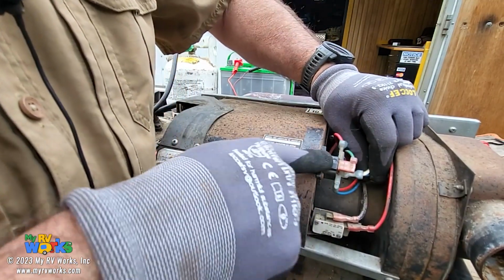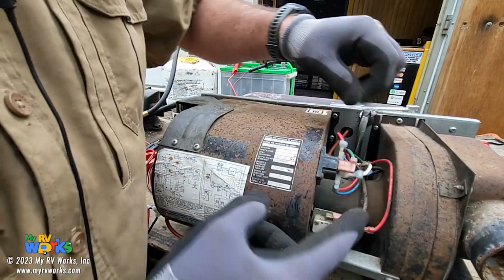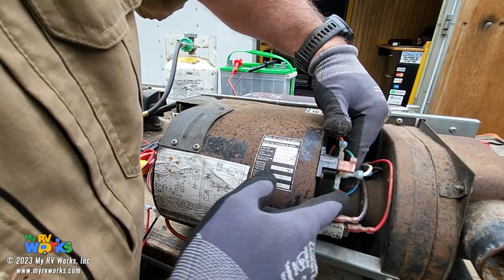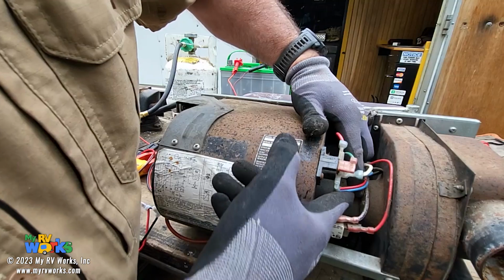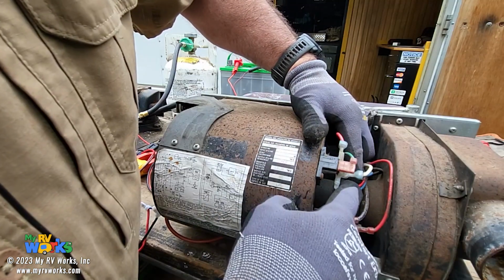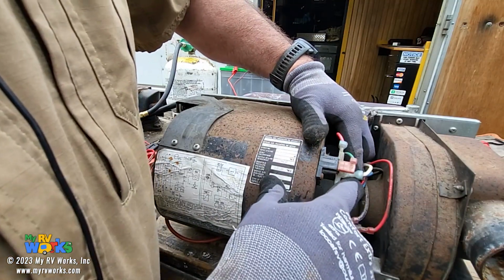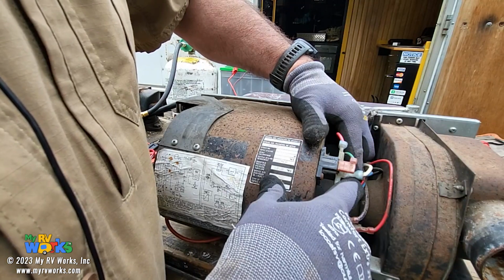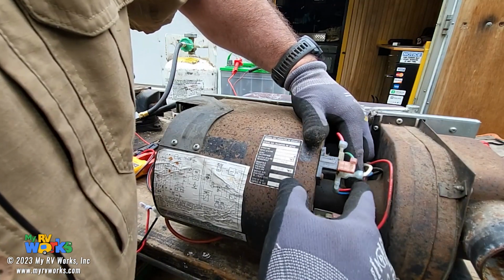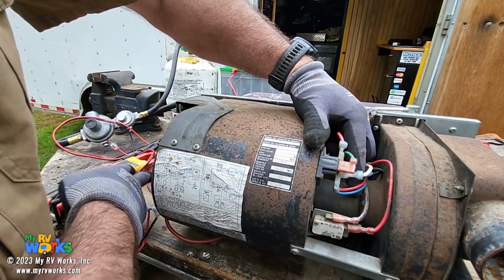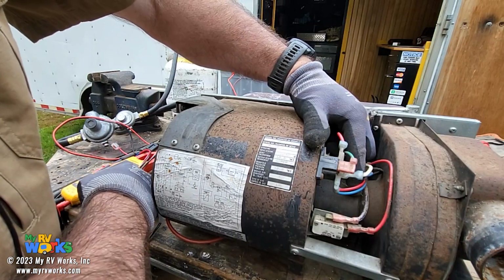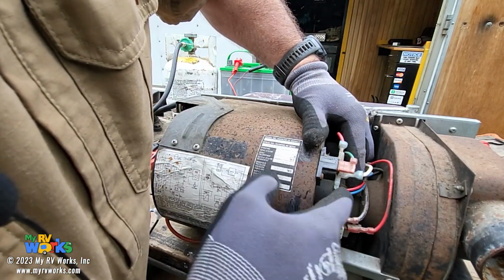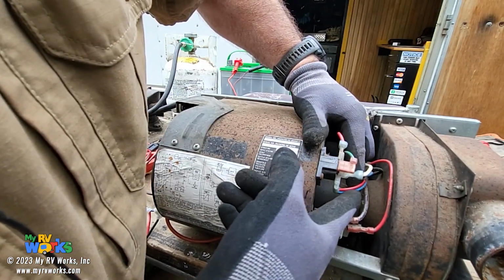Let's talk about this time delay relay for a second. This red wire here that's paired with the blue is the always hot wire. As long as I have power coming to my furnace through my fuse, this red wire is hot. It's the same red wire we saw over here feeding with the red and the yellow. They daisy chain off of the red wire, and they're going to feed this blue wire below it.